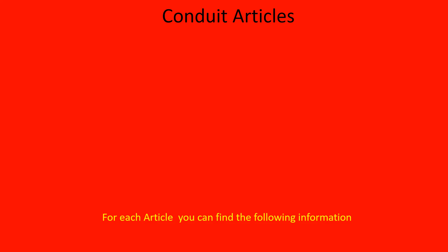For each one of these articles, you can find the following information. If that relevant article has a dot two section, it's going to be the definition of that type of conduit or raceway. If it has a dot 10 section, it's going to have the uses permitted — where can you install this conduit and what can you do with it. If it has a dot 12 section, it's going to have the uses not permitted. Also, if it has a dot 30 section, it's going to be the securing and supporting. And if it has the dot 80 section, it would be for ampacity — that only applies if your raceway has pre-built cables inside of it, which is the case for a couple of raceways we'll talk about today.